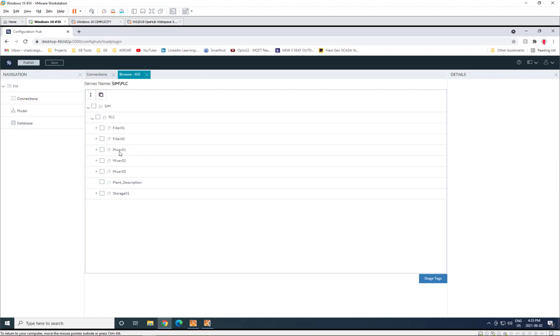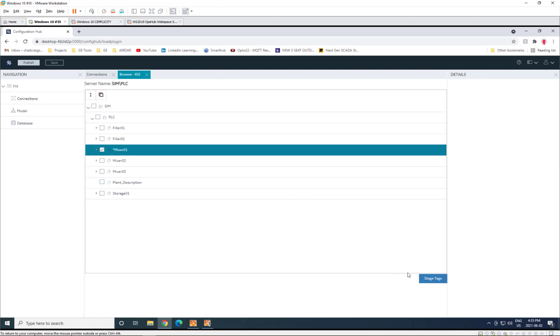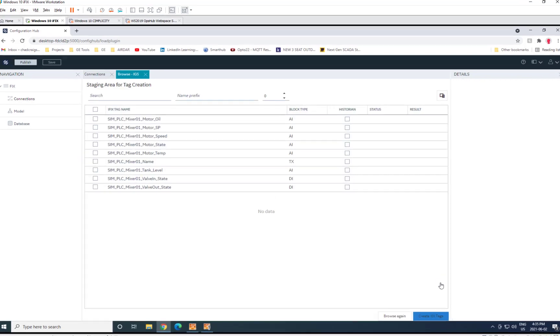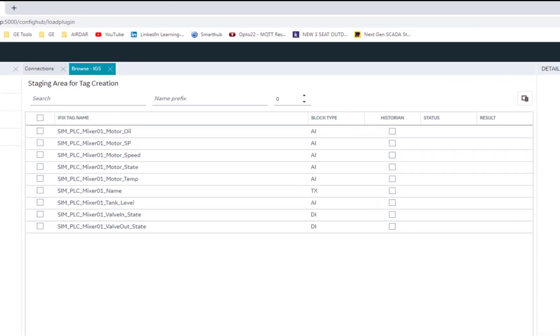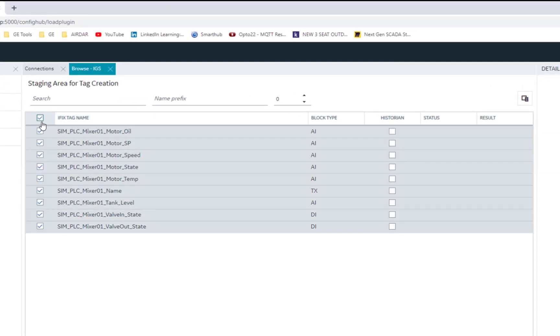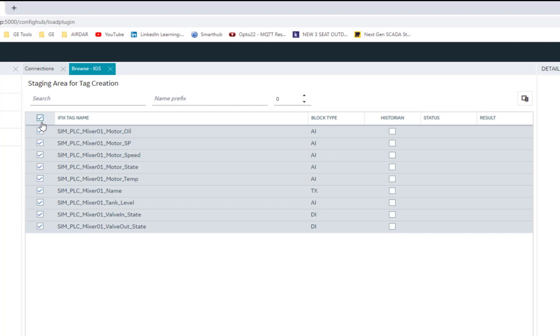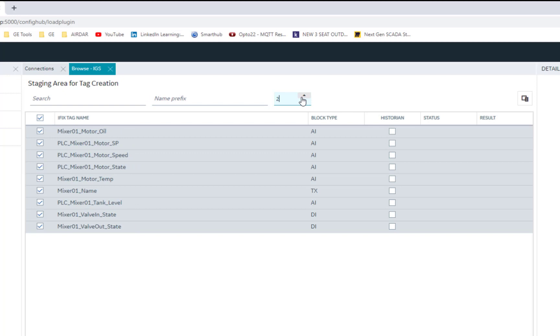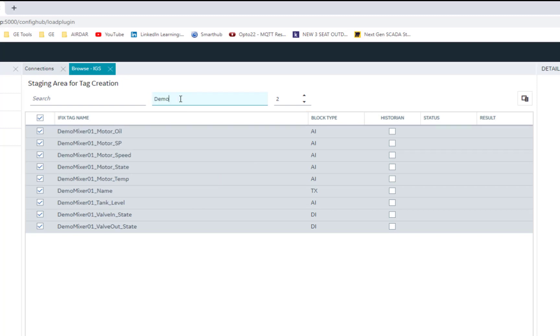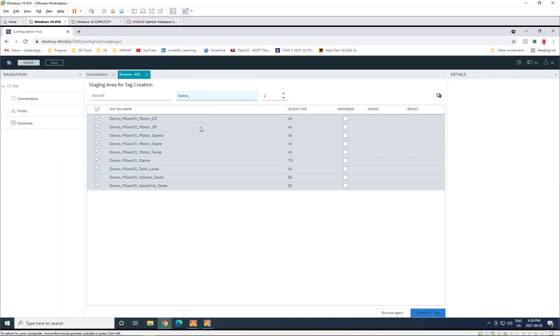So for the purposes of this demo, we're going to bring in all of the points for Mixer 1 in this configuration. To do that, we select Mixer 1, hit Create Tags, and we can select all the tags that we want to be created. We can modify their names by removing some of the hierarchical levels from the tag groups and potentially even put a prefix on it. So we'll call it demo underscore Mixer 1, and then all of the Mixer values are there. So we'll go ahead and create those tags.